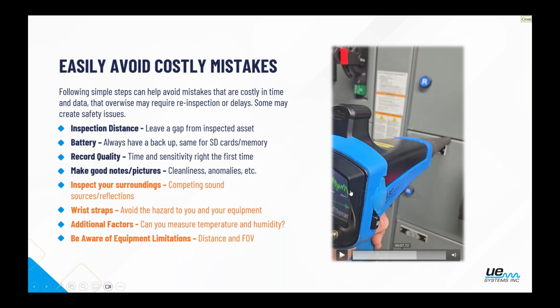for you right here. So I actually have my FFT and time waveform on display on this camera, and you can see impacting events on there from where that boot is contacting the cabinet. Now, if I had just done that one brief time, not actually dragged it all the way across, I might have heard that crackling from that foam on the cabinet and thought, was that possibly an electrical event? Was that tracking, that cracking? Was it something mechanical? So now, because I didn't leave a good healthy distance to inspect from, I'm going to be wasting a few minutes trying to hunt down a sound that doesn't actually exist inside that cabinet. So just be mindful of your distance that you're inspecting from.